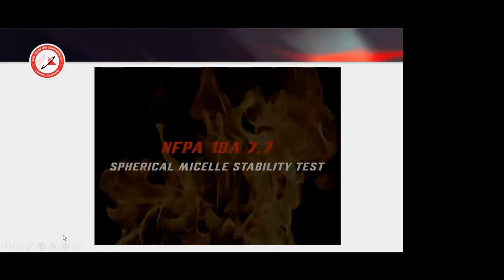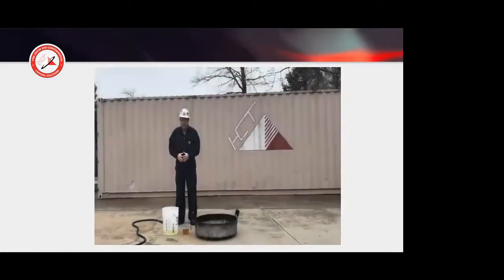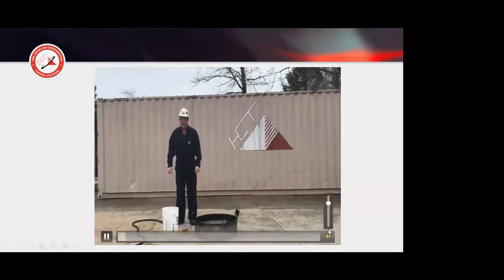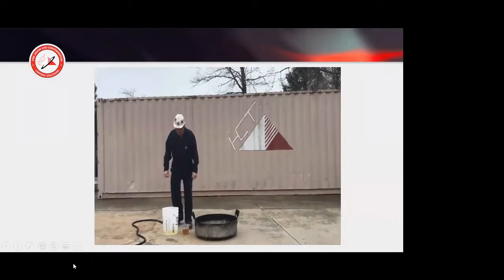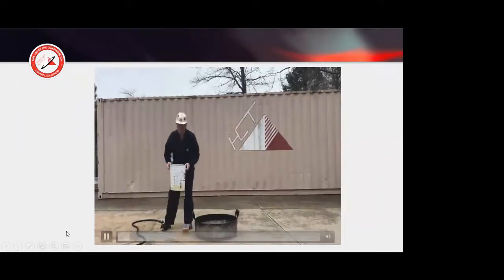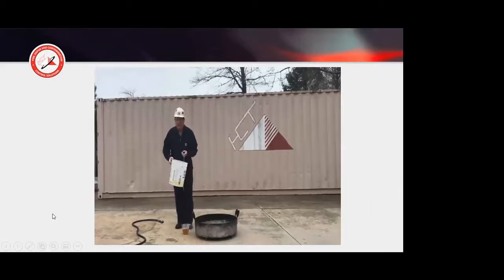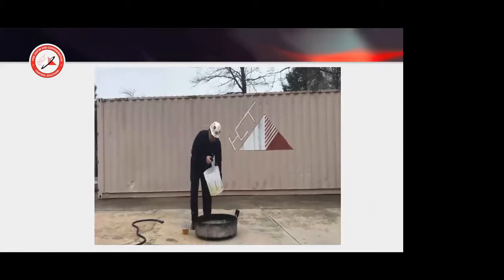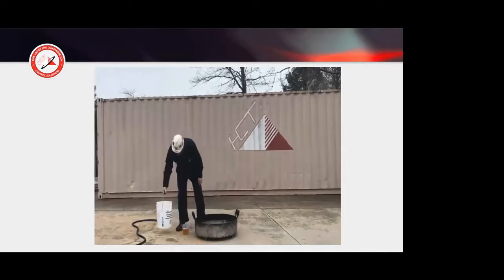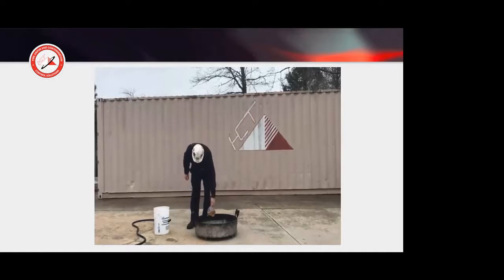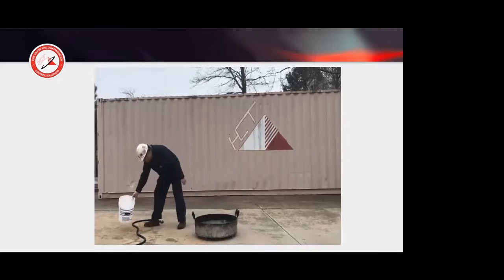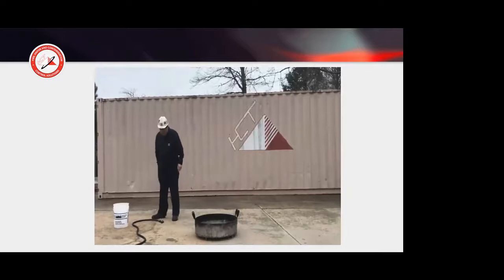So this is the spherical micelle stability test. Here we're demonstrating the NFPA 18A section 7.7 spherical micelle stability test. So in that test, we're mixing in a gallon of gasoline here. The test allows you to test gasoline, heptane, alcohol, any type of fuel, just to demonstrate that. So when you go through your listing process, you will have to test each fuel so that we can determine, does this agent create spherical micelles capable of encapsulating the fuel?